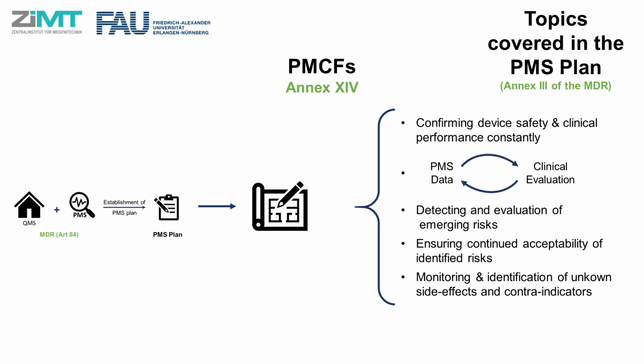The PMCF plan describes methods and procedures used for collecting and evaluating clinical data from the market in order to constantly confirm the safety and the performance of the device. The PMCFs are deeply connected to the clinical evaluation of the medical device. The clinical evaluation shall be periodically updated with the clinical data collected from the PMS through the PMCFs.